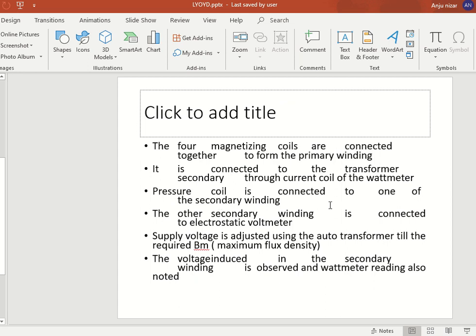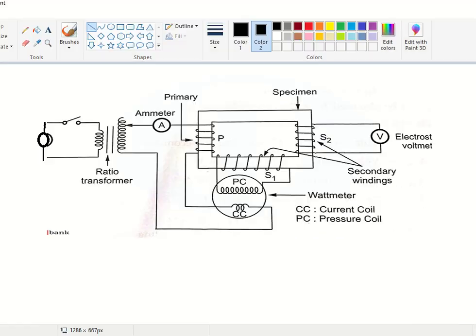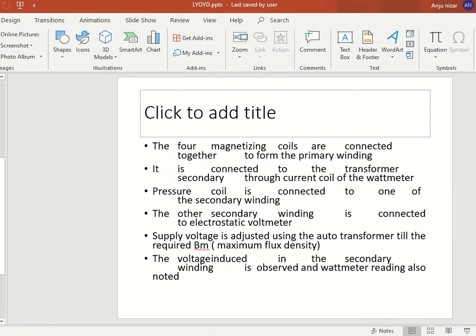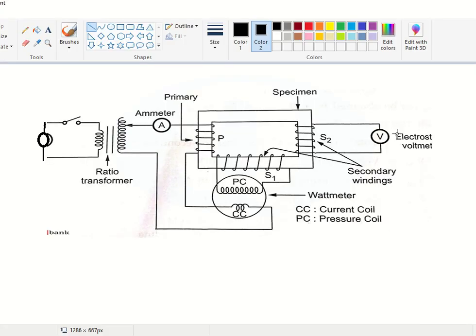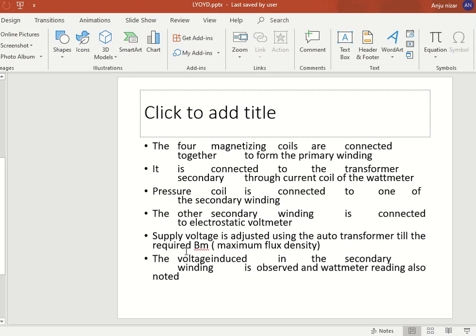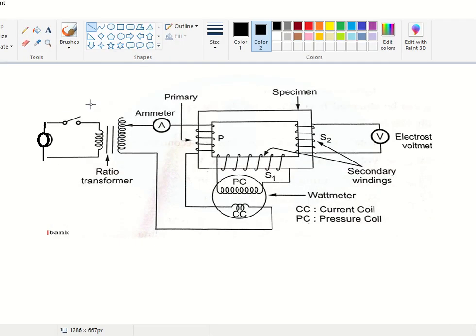The pressure coil is connected to one of the secondary windings, S1. An electrostatic voltmeter is connected to the other secondary winding S2. The supply voltage is adjusted using the auto-transformer until it reaches the required maximum flux density. Note down the readings of the wattmeter and the electrostatic voltmeter.